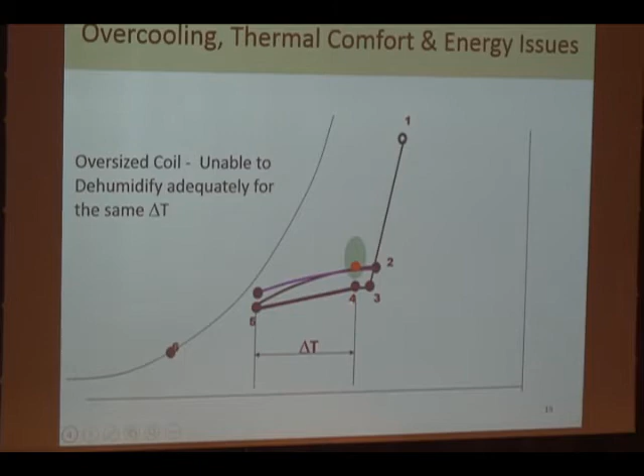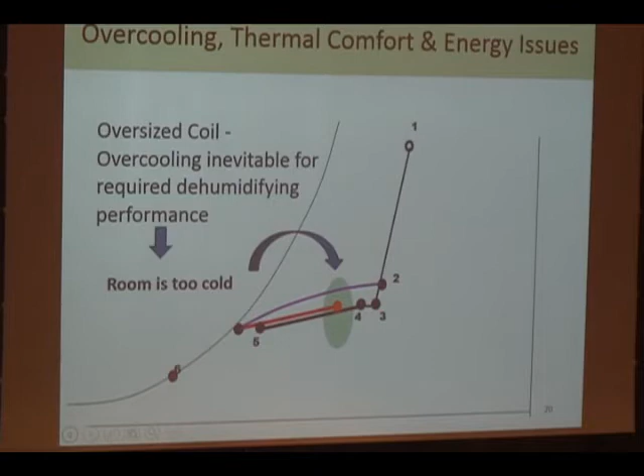So that's what causes overcooled buildings. You either have overcooled buildings with maybe the humidity addressed properly, or you have a situation where the humidity is not addressed properly and you have a bit of a stuffy environment. So this is the hypothesis I'm presenting or starting off with: we have an overcooled building simply because the coil is incompatible.